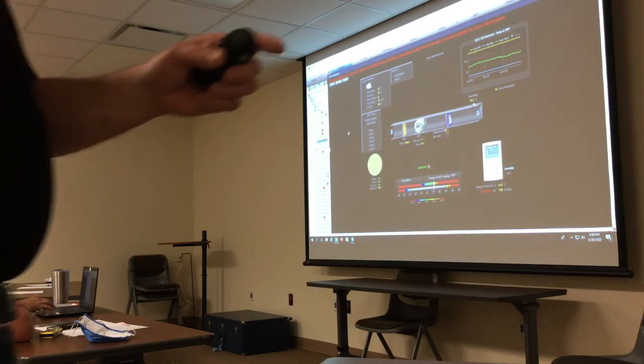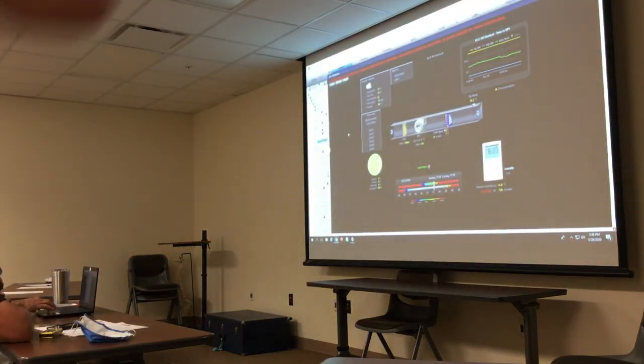Alarm actions is a really good one, so you know where alarm actions reside. When we're setting up those email and text messages to go out to you, at least you know where they're coming from in the system. It's best not to set them up at each piece of equipment individually - it's better to do them high so it catches all those alarm types when we filter them. But it does let you know where they're at.